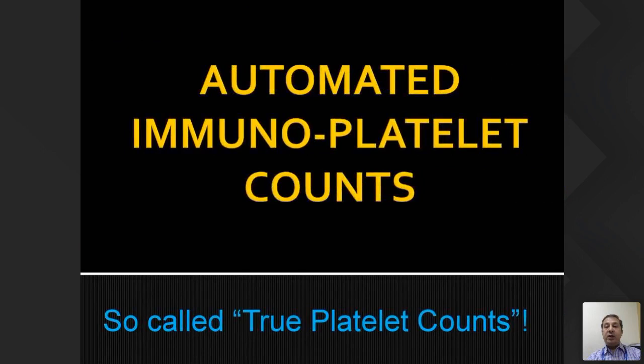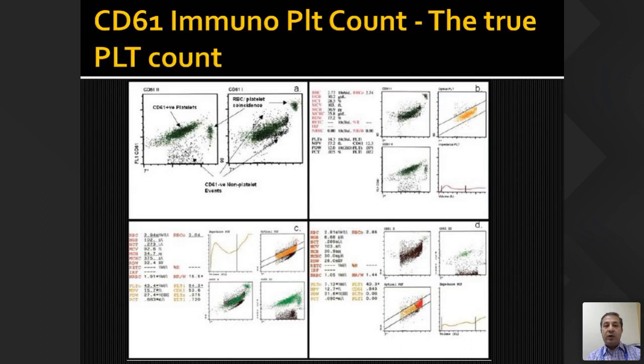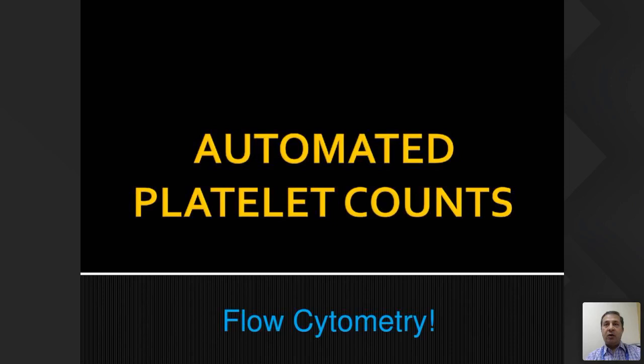Automated immunoplatelet counts are claimed to be 'true platelet counts.' One instrument from Abbott uses CD61 immunostain for platelet counting — because it identifies platelets very specifically, it gives exact platelet counts that correlate very well with flow cytometer results. The biggest challenge is cost: where a normal platelet count costs 20–50 rupees, this methodology costs at least 200–300 rupees.